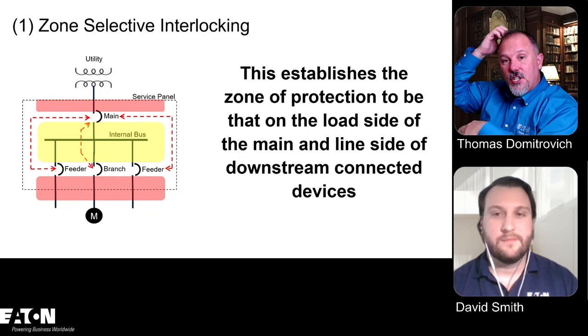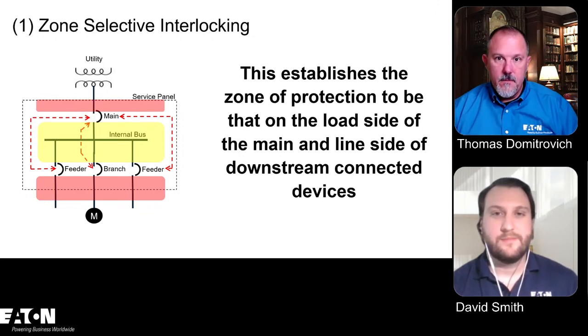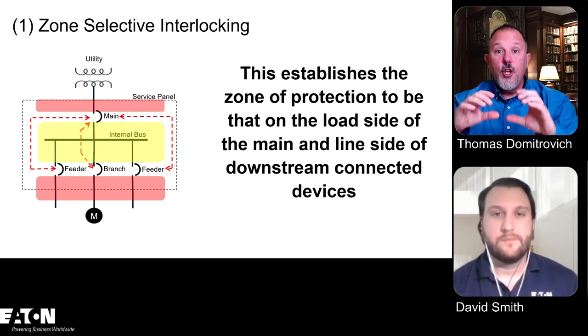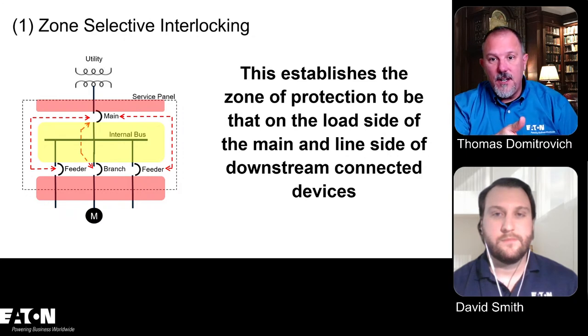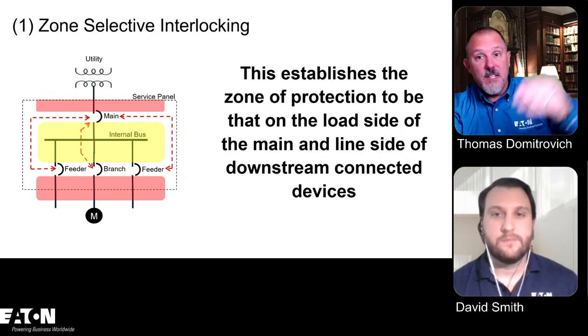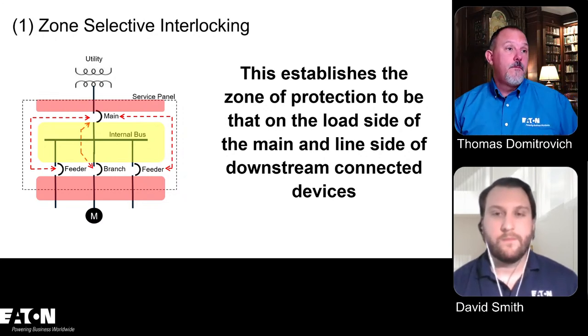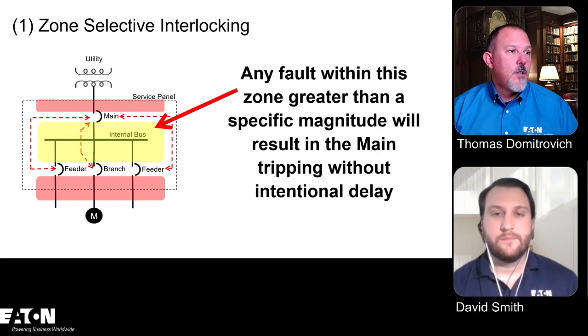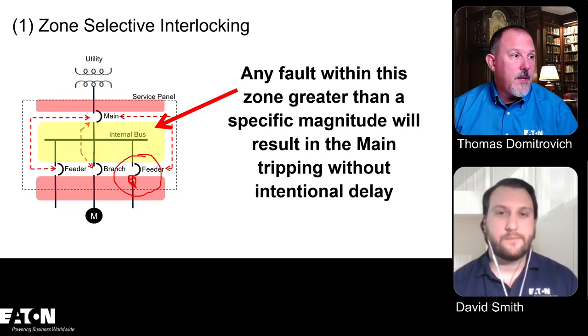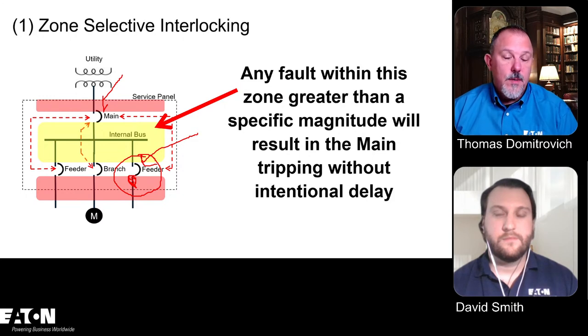So to Ross's point about line side propagation, all that good stuff, zone selective interlocking does not look downstream. It provides protection in this zone. Your fault has to happen on the line lugs of those branch or feeder breakers downstream and on the load lugs of the main overcurrent device. Got it. That's where the fault has to occur, and that's when you're in the zone of protection. So any fault in that zone is protected, and if you're in that equipment and you touch down here, your clearing time is going to be based upon the clearing time of that device. If this is a low voltage assembly, and that's, say, a 4,000 amp breaker with a 30 cycle delay, and this is a 2,000 amp breaker with a 20 cycle delay, or an 800 amp breaker if it's lower, right, you're going to be dependent upon that, not ZSI.